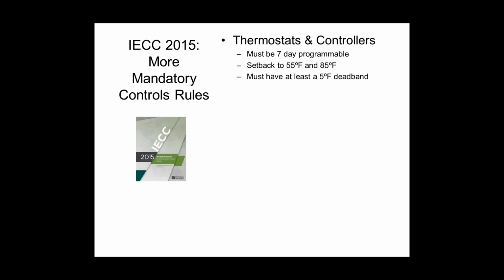What does that mean? That means in the stat, you have to have it programmed, configured such that the heating and cooling set points are always forced to be 5 degrees apart from each other. So if you want to have 70-degree heating and 75 cooling, that is fine. If somebody goes up to the stat and bumps the cooling set point from 75 down to 73, it has to automatically force the heating set point from 70 down to 68 to maintain the 5-degree dead band in there. Lots of thermostats do that. They are typically defaulted to 2 degrees. You need to change them to 5.